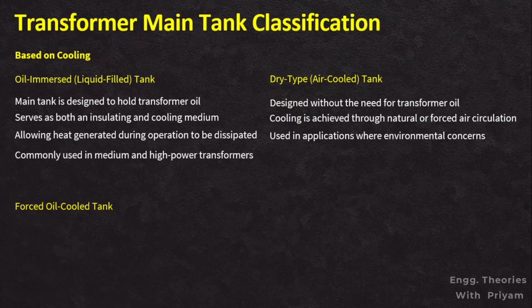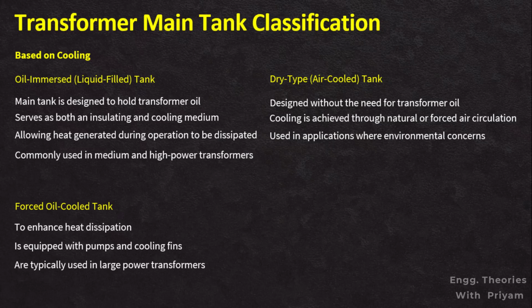Some transformers use forced oil cooling system to enhance the heat dissipation. The main tank is equipped with pumps and cooling fins or tubes to circulate the transformer oil more efficiently, increasing the cooling capacity of the transformer. Forced oil cooled transformers are typically used in large transformers or in applications where higher cooling rates are required to handle the increased loads and ambient temperatures.